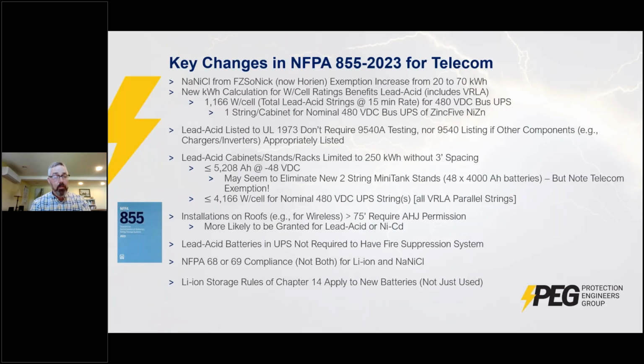So for lead acid and NiCad, it's 70 kilowatt hours. For lithium-ion, it's 20 kilowatt hours. Sodium nickel chloride was able to increase their threshold quantity from 20 kilowatt hours to 70 kilowatt hours by bringing test data to the committee and showing them that it's relatively safe, what its failure modes are, and how it performed in various tests like UL 9540 and 9540A and so forth.